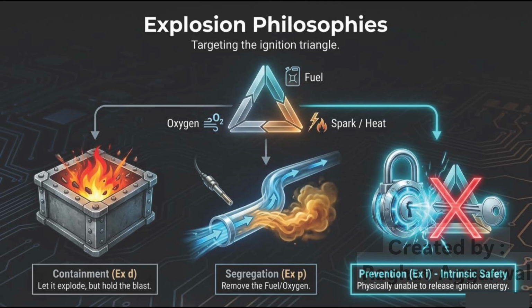There are three different approaches to explosion protection. At the center is the ignition triangle, consisting of fuel, oxygen, and a source of ignition such as a spark or heat. An explosion typically requires all three elements. The first approach is containment, identified as Ex d. The concept is to allow an internal explosion to occur while ensuring the enclosure contains the blast. The second approach is segregation, identified as Ex p. Here, the goal is to remove access to fuel or oxygen.